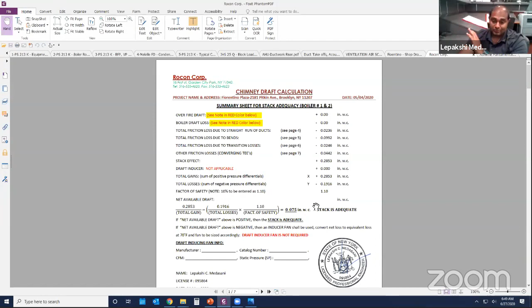You have to make sure whatever the system that you are designing is going to be working. So first we talked about the combustion air. Now you talk about the exhaust gases freely dumping that stuff outside. So you have to make sure you have enough draft. In this case, we do have enough draft, so we don't need any draft inducer fans. For instance, if you don't have enough draft, which means if the losses are more than the gases being generated in the boiler, they're not going to go outside. They're going to stay there.